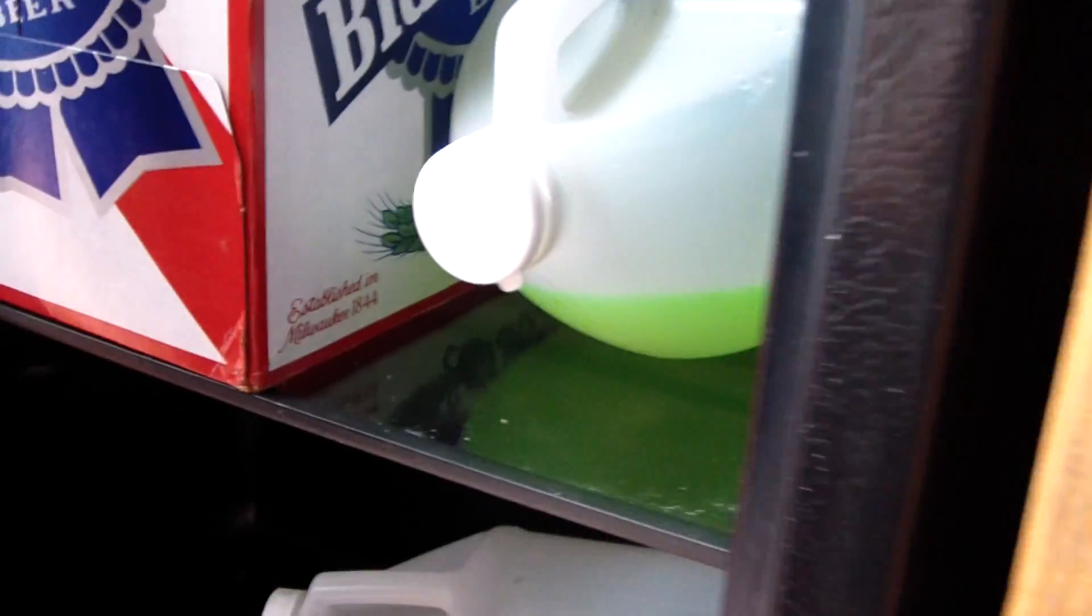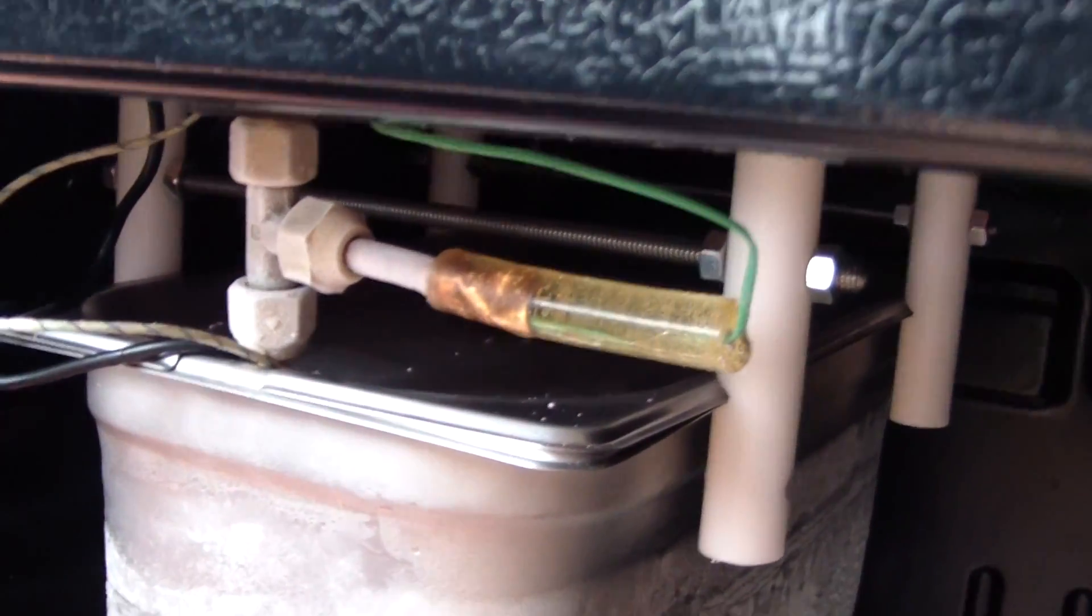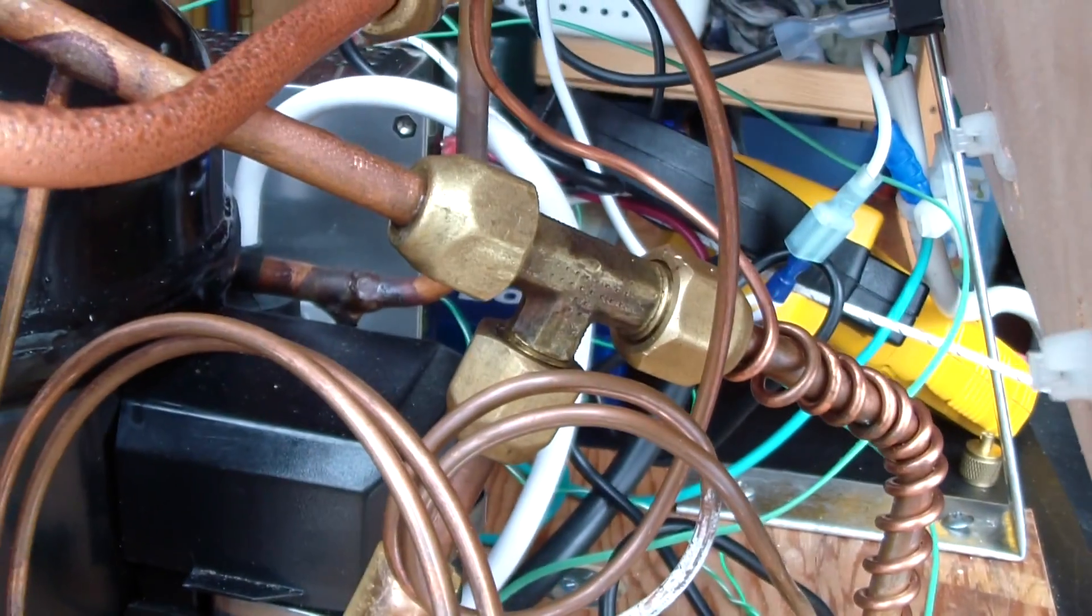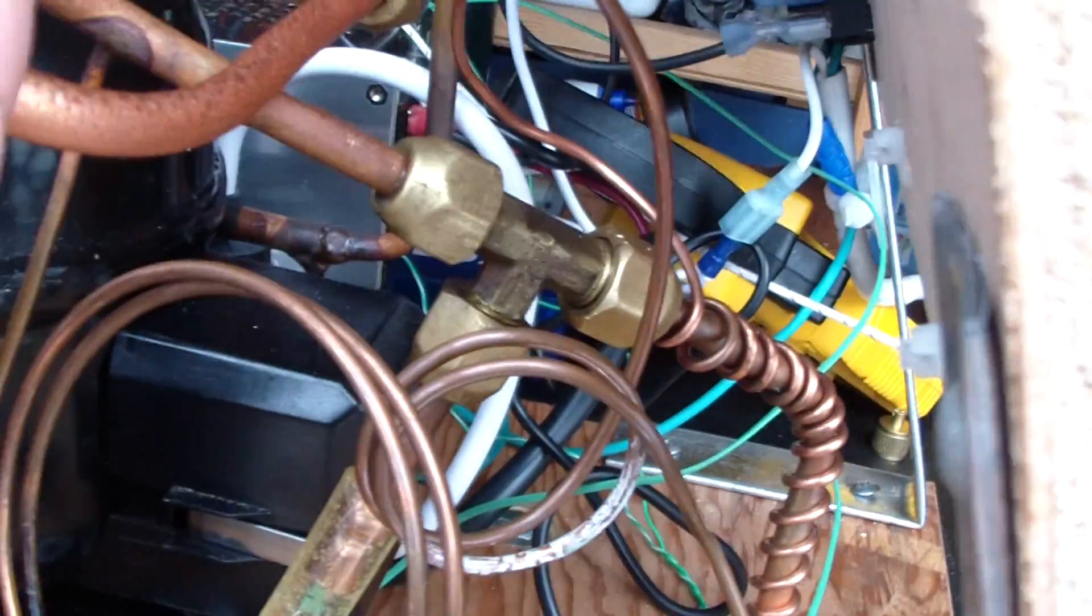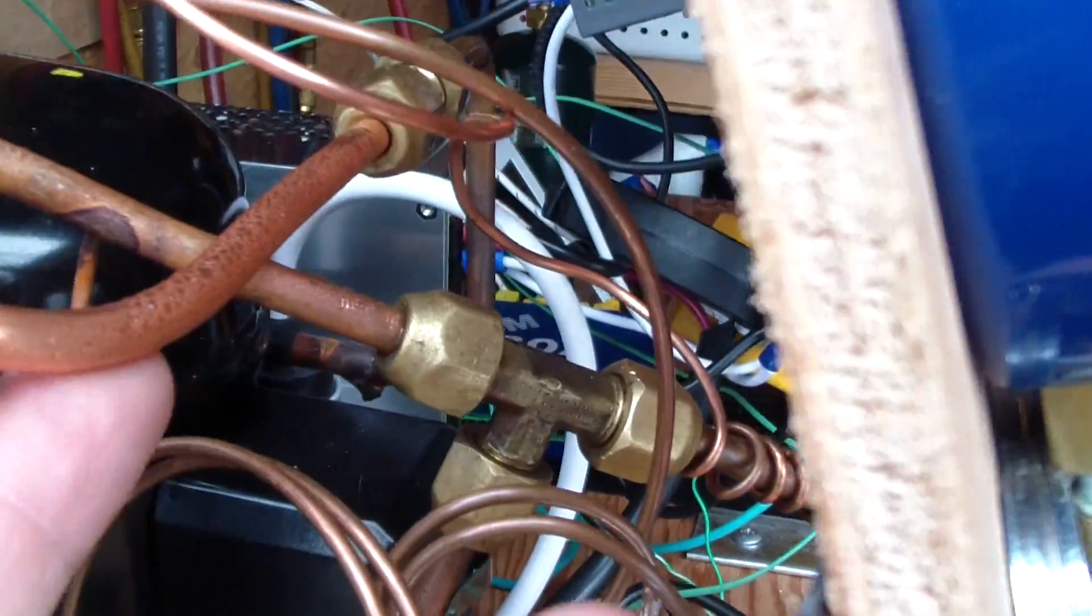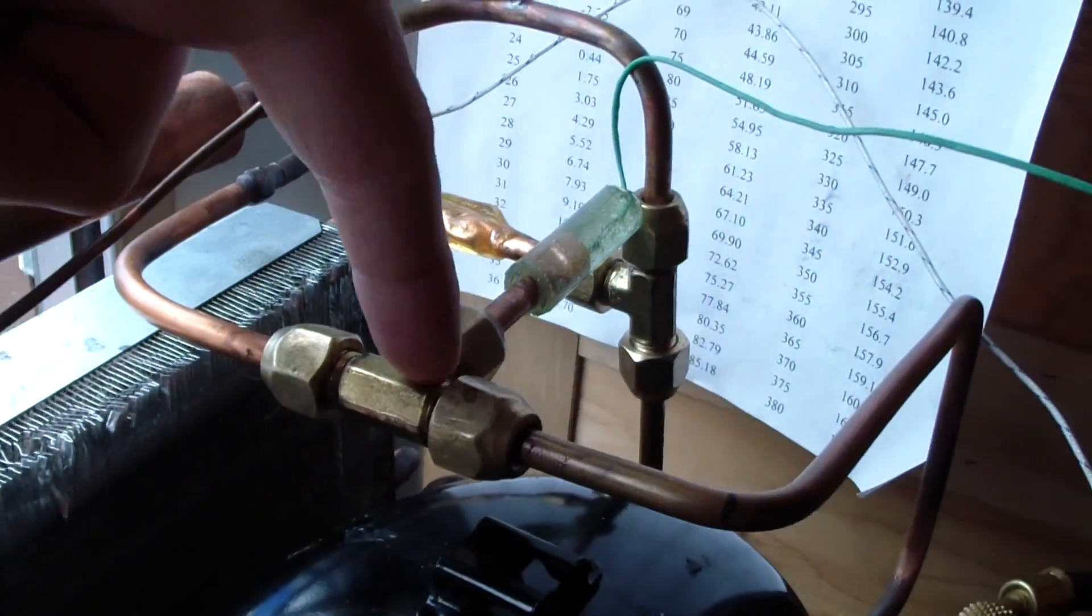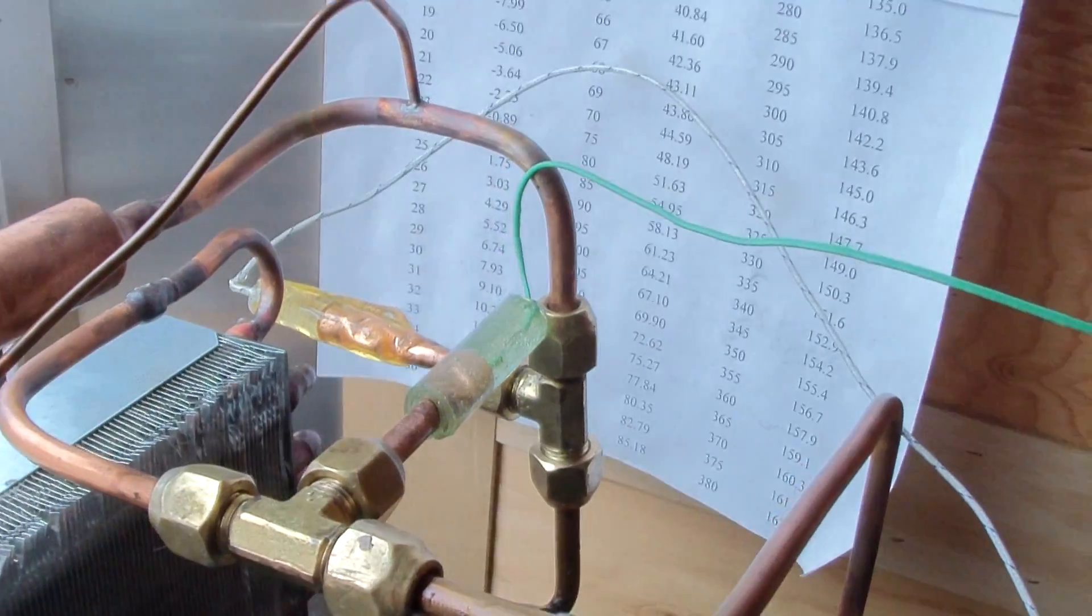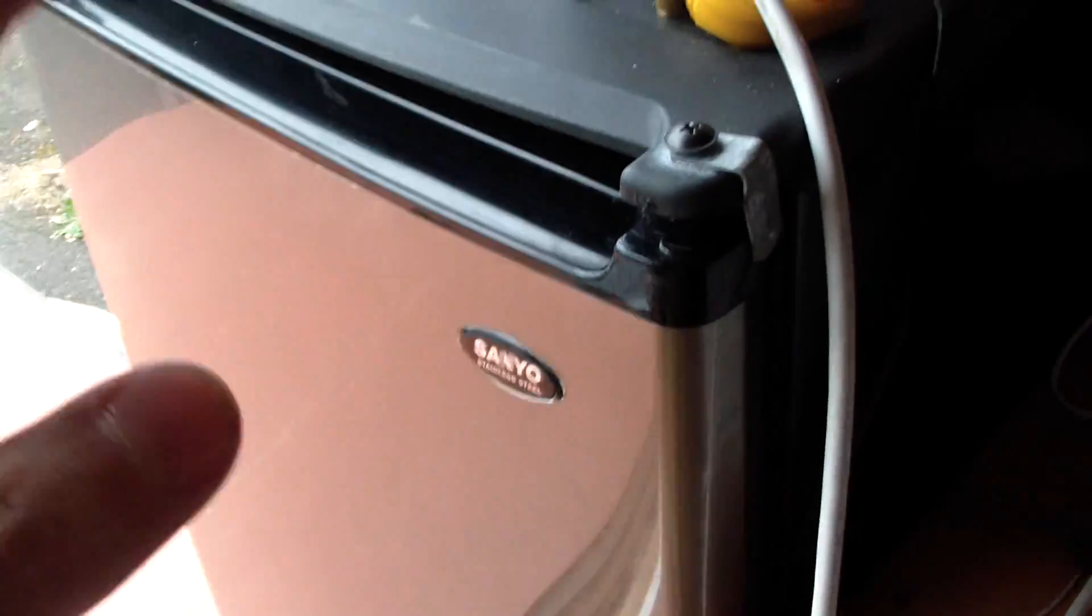Additionally I've got glass shelves in this thing, whereas I'll probably replace them with wire racks. For sensors, I have a suction thermocouple there in line. I have a second suction thermocouple in line right there at that T in the center of the frame. One's before the heat interchanger, one's after. These lines are all going to get insulated eventually. I just do this for demonstration purposes. Additionally I have a discharge superheat in line, I have a subcool thermocouple in line. I also have a thermocouple in the bucket of coolant and also one for air temperature.